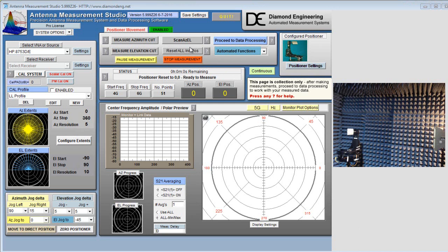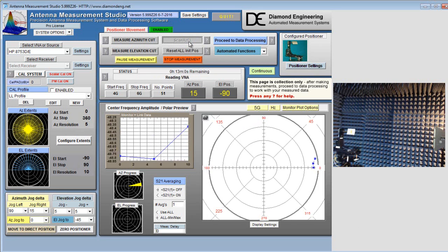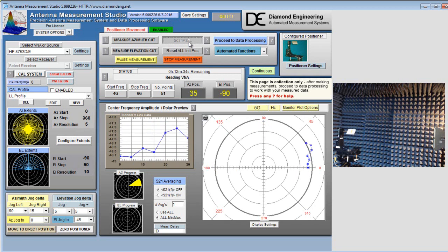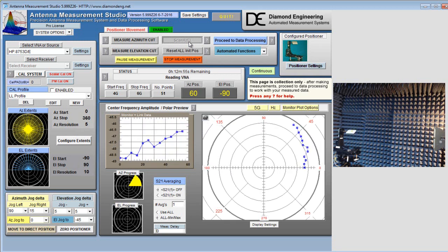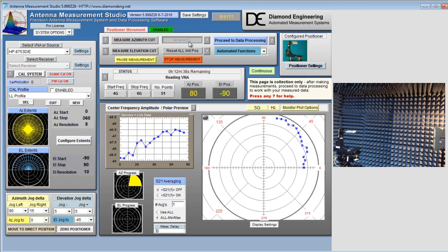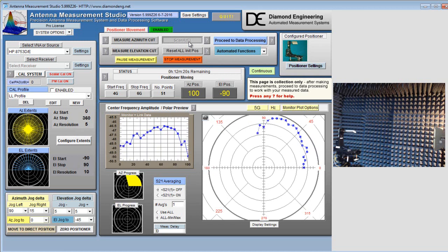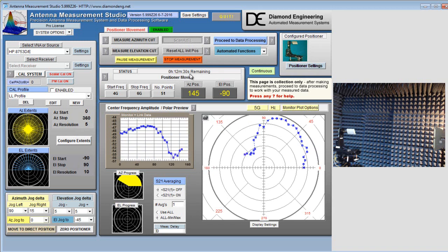We will now press the ScanAzEl button to perform a full spherical measurement. The positioner will rotate to its starting theta position, or elevation, and it will start collecting azimuth or phi cuts around the antenna until it has completed. The estimated time says we have about 12 minutes left to complete this cut. The video will resume when the measurement has completed.